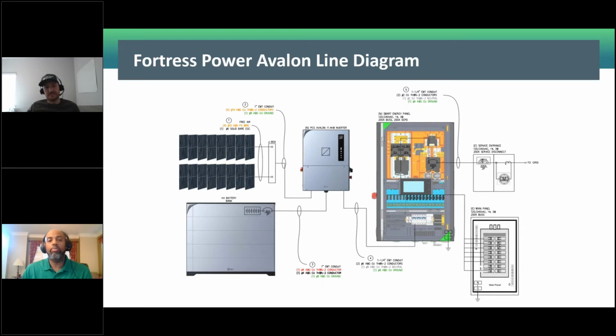This is really the special sauce, because it eliminates the need to wire a separate critical load panel. Now you essentially have your power circuits, and you don't have to reconfigure the load center. You put those 3 power circuits on this side of the smart energy panel, and you can add a breaker here up to 200 amps as well. This has a 200 amp bus capacity. You control those circuits through the load shedding management functions down here for your 3 power circuits, plus the 12 single pole or 6 double pole circuits. Those are the loads you're now managing and shifting, just wiring from your load center.